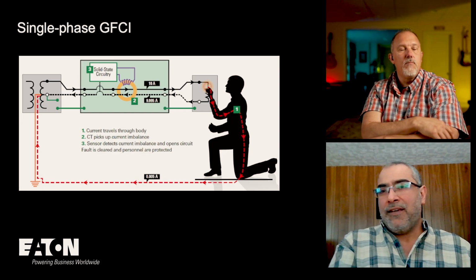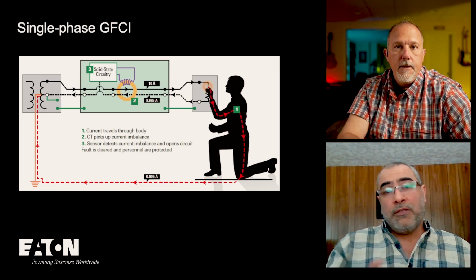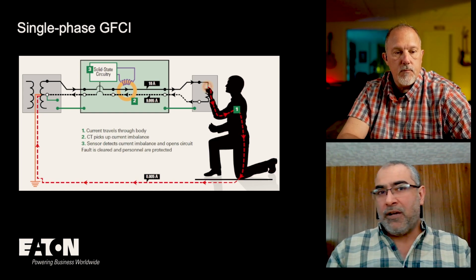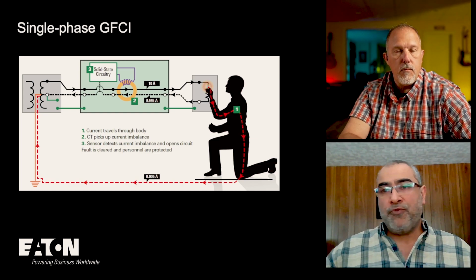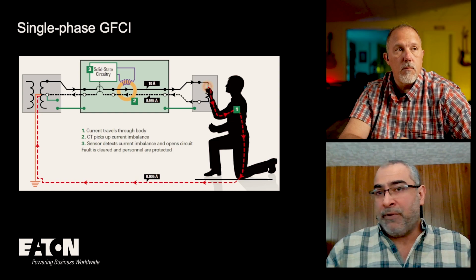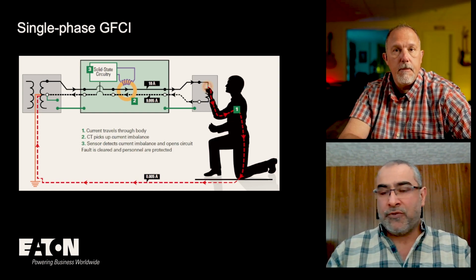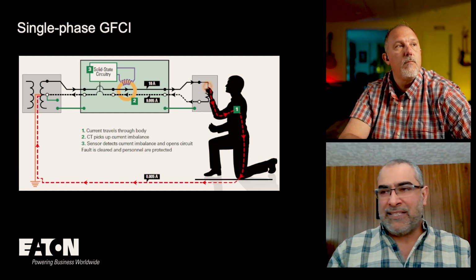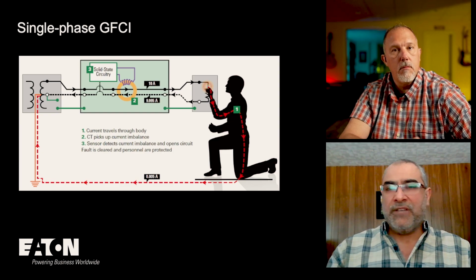So we try to test at something that is very, very low. That doesn't mean 500 is the lowest, because if this person is swimming, the resistance could be 200 or 300 ohms because of the water and other conditions. But 500 ohms has been the standard in UL testing for GFCIs to represent human body resistance.